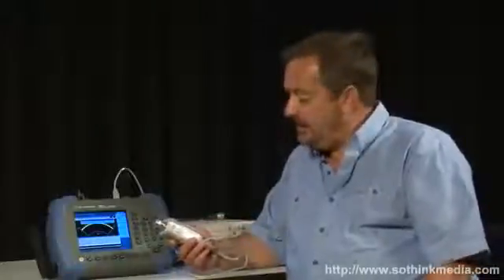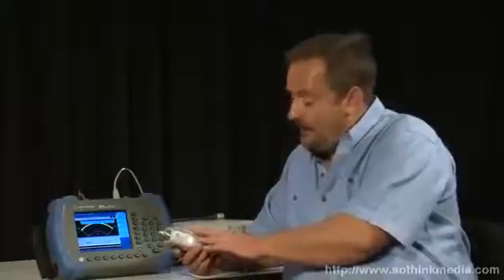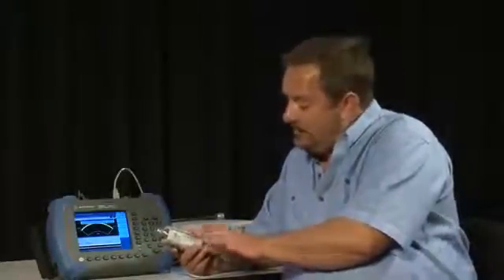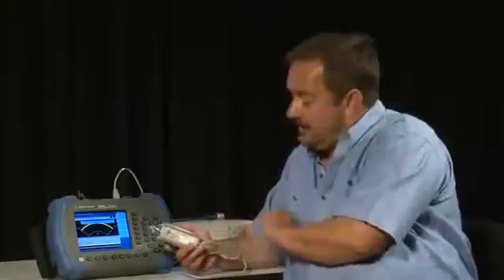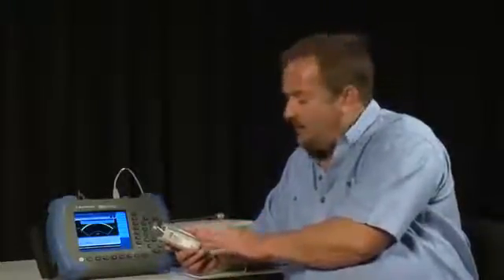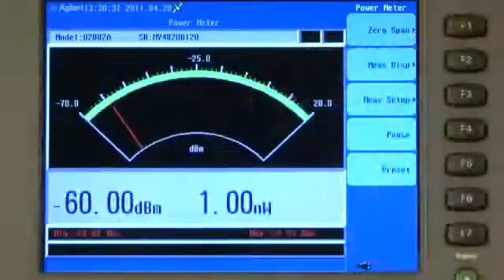And it's a good time to point out that unlike a normal power sensor meter whereby you have to manually enter the calibration factors for that particular sensor into the meter to get an accurate measurement, with the U2000 series the calibration factors are automatically loaded in. They're stored in memory inside the unit. Plus you don't have to zero or calibrate the sensor. It's auto-zeroing, auto-calibrating. So the sensor is now recognized and it's all working.